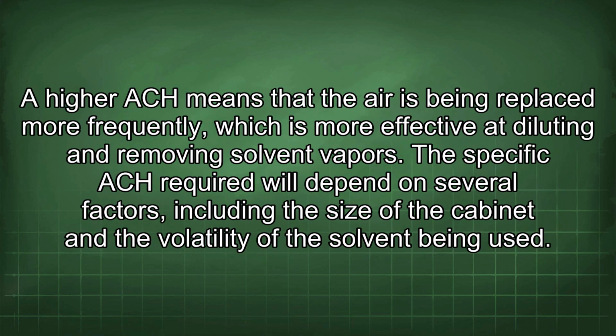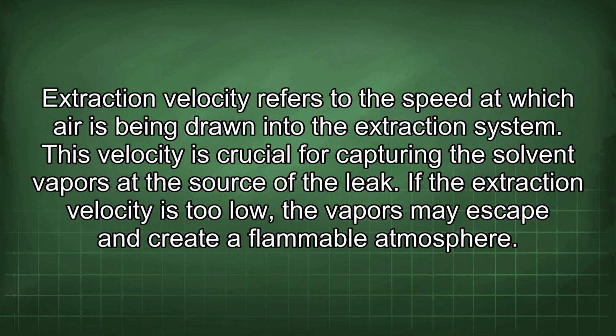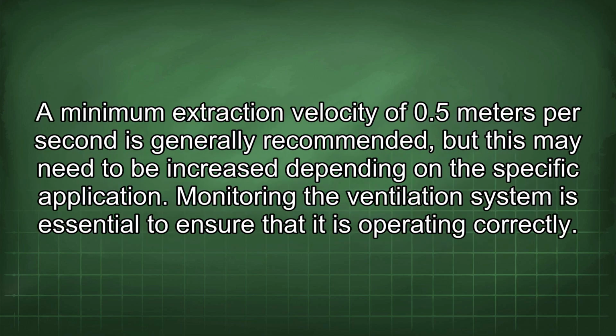A higher ACH means that the air is being replaced more frequently, which is more effective at diluting and removing solvent vapors. The specific ACH required will depend on several factors, including the size of the cabinet and the volatility of the solvent being used. Extraction velocity refers to the speed at which air is being drawn into the extraction system. This velocity is crucial for capturing the solvent vapors at the source of the leak. If the extraction velocity is too low, the vapors may escape and create a flammable atmosphere. A minimum extraction velocity of 0.5 meters per second is generally recommended, but this may need to be increased depending on the specific application.